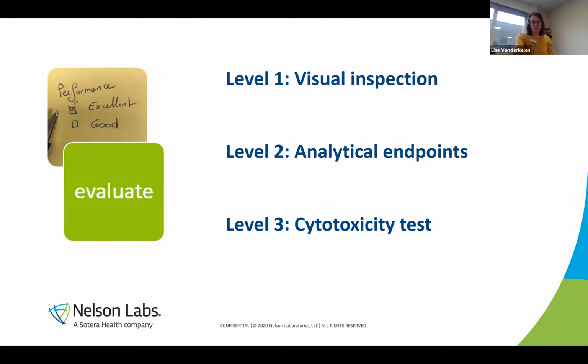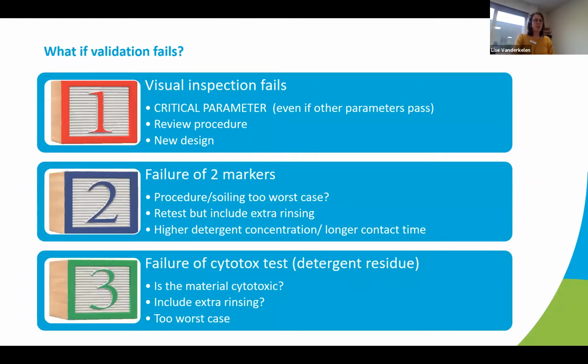What do you do in case of failure? If level 1 fails, it's one of the most critical parameters because it's used in the clinical healthcare facility. You have to review your procedure. It can be a new design. It's almost always seen already during the simulated use. If the 2 markers fail, you might look at procedures, soiling too worst case. You might include an extra rinsing step or a higher detergent concentrate. You have to see, did I make my balance between soiling and cleaning correct? Can also be a new design. And if your cytotox fails, also there, did I overdo it? Did I do it too harsh? But sometimes you also have to wonder, is my device already without a cleaning cytotoxic or not? We had a situation where that was the case, that the device itself was already cytotoxic even without a cleaning step, and then it was just not a good marker to look for detergent residue.